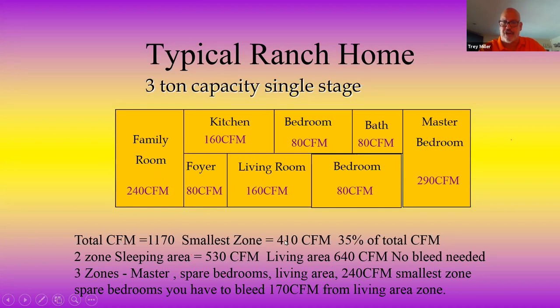240 CFMs is smaller than the 410. Subtract the 240 from the 410, that gives me 170 CFMs. All I've got to do is bleed 170 CFMs to the living area, gentlemen, and I've got a perfect system. It works beautiful. This is all we have to train our contractor on how to do. And then he doesn't have sweating. He doesn't have problems. The problem we have is a guy goes in and wants a 6-inch zone, no bypass. I mean, 6-inch zone, too much bypass, sweating, short cycling on limit. That's not what we want.